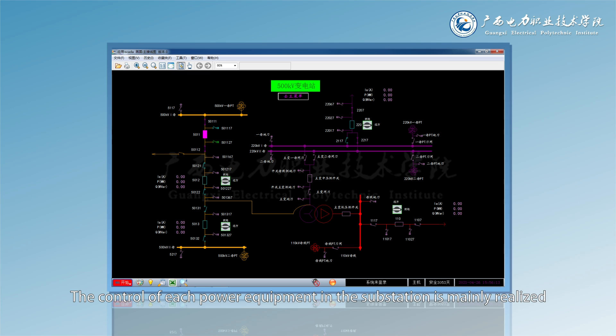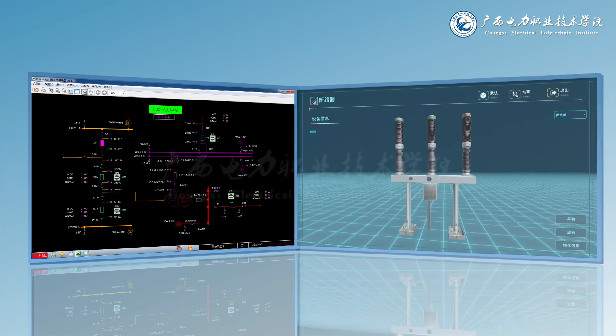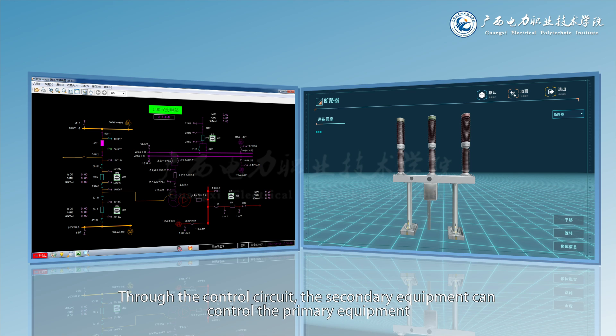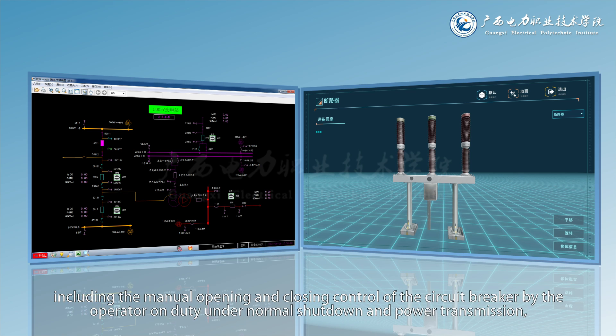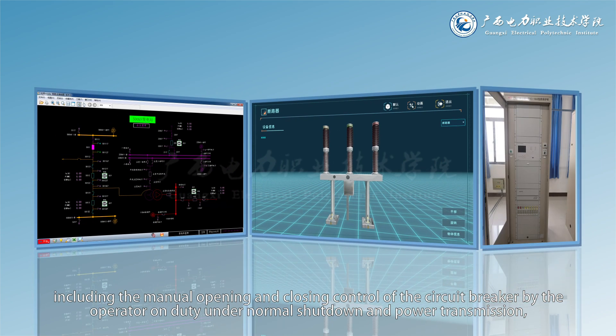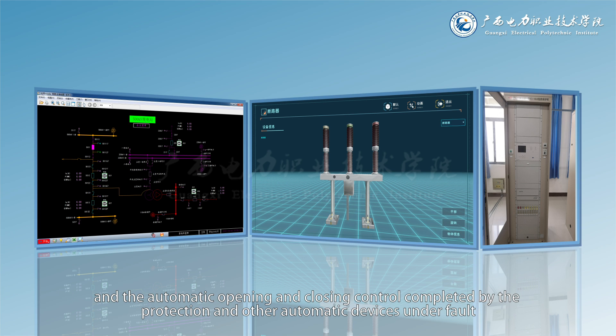The control of each power equipment in the substation is mainly realized through the control circuit and operating mechanism of the circuit breaker. Through the control circuit, the secondary equipment can control the primary equipment, including the manual opening and closing control of the circuit breaker by the operator on duty under normal shutdown and power transmission, and the automatic opening and closing control completed by the protection and other automatic devices under fault.